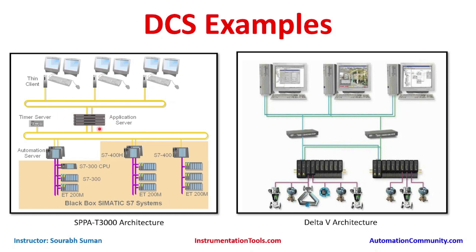The application server sits in between and has multiple NIC ports. The hardware could be an HP DL360, Dell, or Fujitsu server. Windows Server is installed on this hardware, and on top of Windows Server the application software SPPA-T3000 runs. It receives data from both the automation highway and the application network. On the application network, multiple thin clients sit and log into the application server to access the workbench.